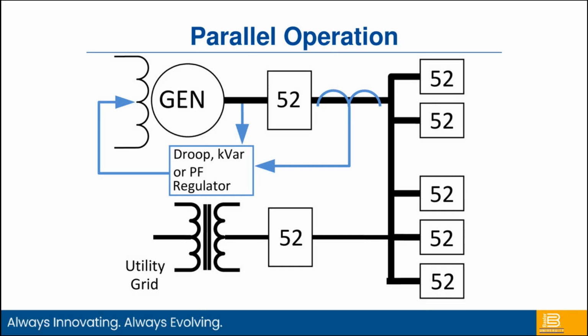Therefore, we also need to look at the current, which will allow us to parallel the voltage regulator, and we can run this in multiple modes. We can run it in voltage droop, in cross current compensation or reactive differential. We can do kVAR control, or we can monitor the phase angle and do power factor control, because now we have the capability, by looking at the difference in the phase angle between the voltage and the current on the output of the generator, to calculate these different parameters and control them.